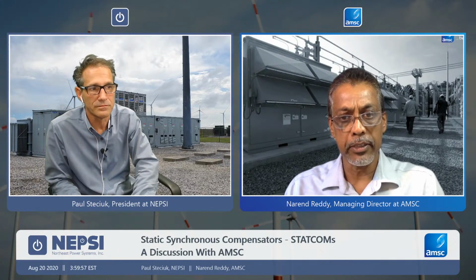Well, I know we talked about it, and it is an important discussion point, and cost is always there as to how much it costs. But it's very important, like I said, to make sure that we concentrate on the application. A cost per megavar sometimes is probably not a true reflection unless we know exactly how many megavars are needed to solve a problem. Why I say that is because a steady state 4 megavar dvar unit costs the same whether it's applied for a steady state 4 megavar requirement or used for a 12 megavar transient requirement. So that cost per megavar can be a misleading figure.